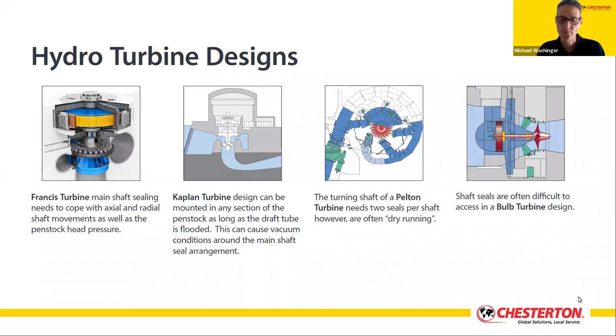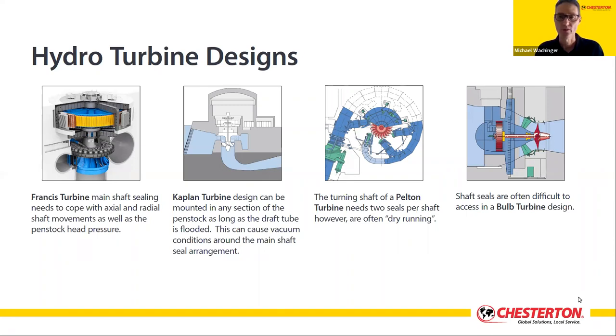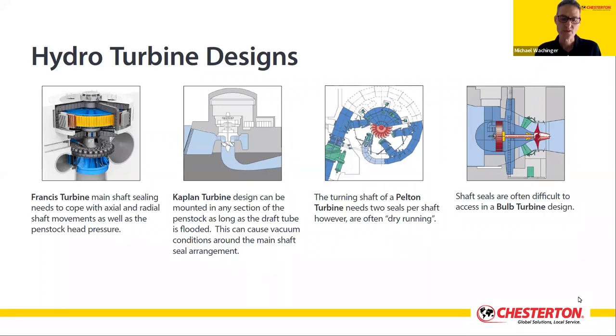The four most popular hydroturbine designs used around the world are the Francis, Kaplan, Pelton and Bulb type turbines. In 1848, James B. Francis improved on an original Fourneyron and Poncelet French design, and by 1920 the Francis turbine became the most common inward flow reaction turbine in use. It has a high efficiency of greater than 95%. Water flow and speed control are governed by wicket gates or guide vanes. It's best located at the bottom of a penstock, and the main shaft seal needs to cope with both axial and radial shaft movements as well as penstock head pressure.